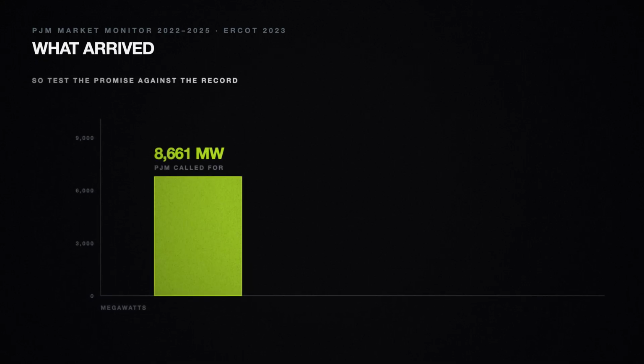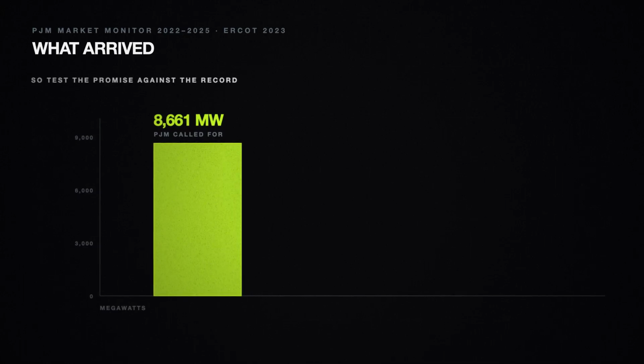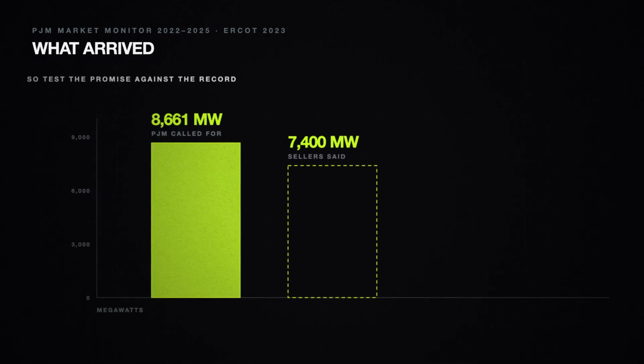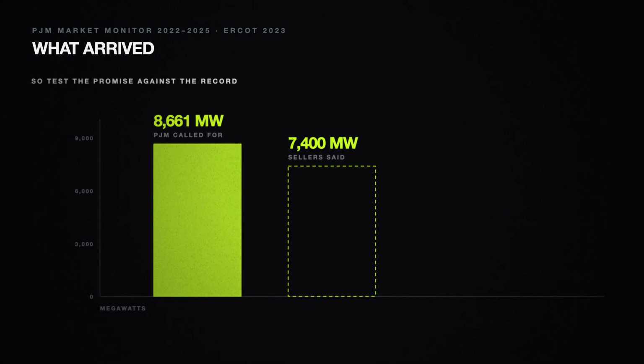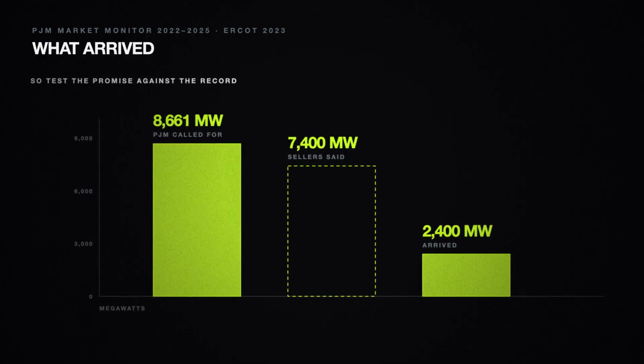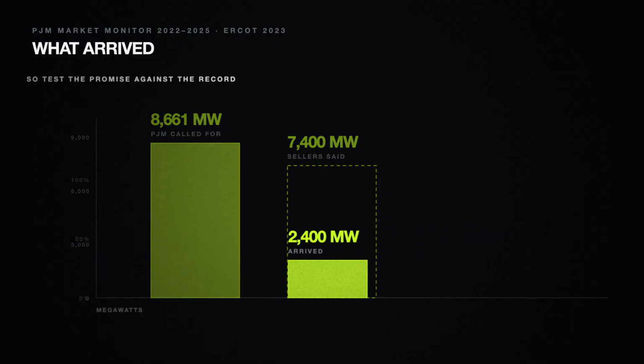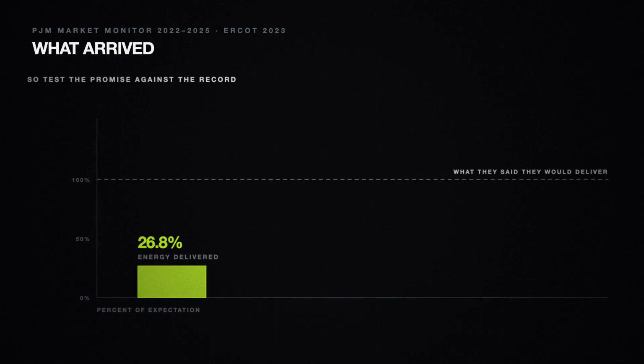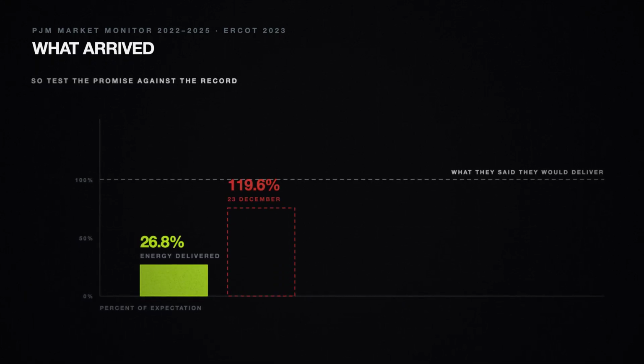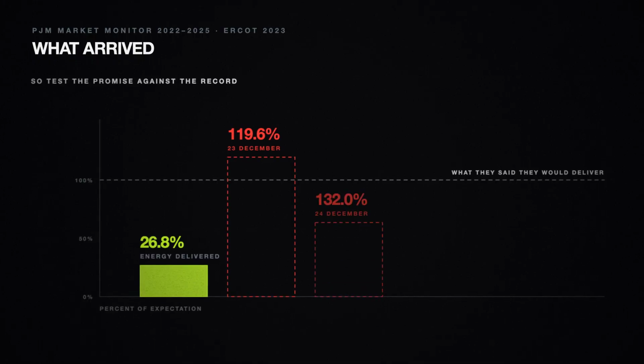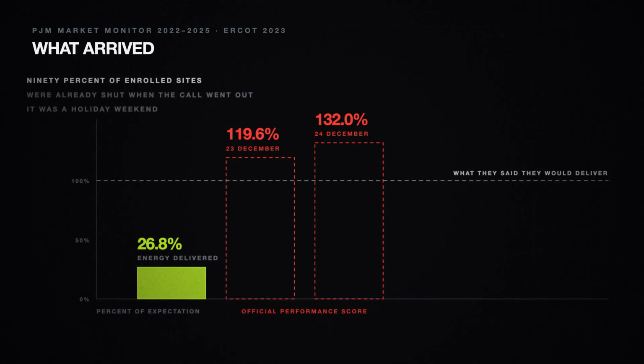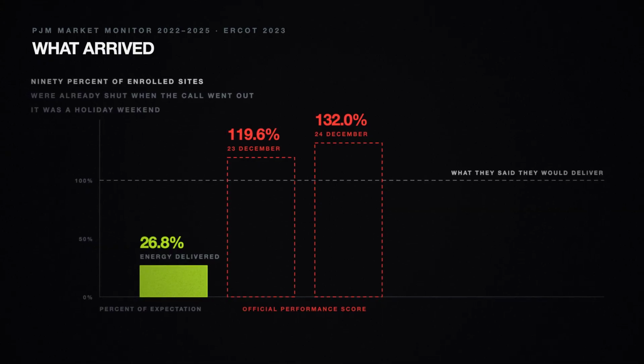So test the promise directly, not the model, the record. December 2022, Winter Storm Elliott. The largest eastern grid called on its demand response program for 8,661 megawatts. Providers said they could deliver 7,400. 2,400 arrived. Across both days, the energy delivered was 27% of what the sellers had forecast. The official performance score for those days was 119% and 132% because 90% of enrolled sites were already shut. It was a holiday weekend. The factories closed before the phone rang.